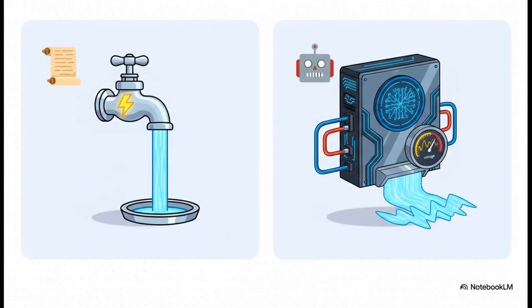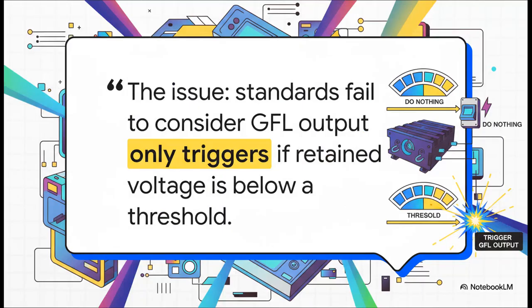So here is the massive disconnect. The standards drastically, and I mean drastically, oversimplify things. They basically model a super sophisticated inverter as a dumb, constant current source that just blindly injects, say, 1.1 to 1.5 per unit current anytime there's a fault. The physical reality? The inverter's output is this complex, highly voltage-dependent response that's all managed by its fault ride-through control logic. And here is the killer detail, the one thing that breaks the whole model.